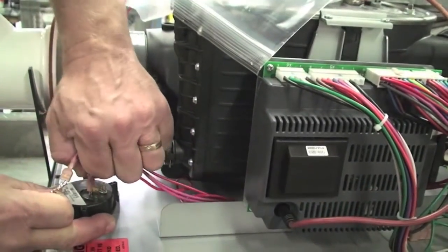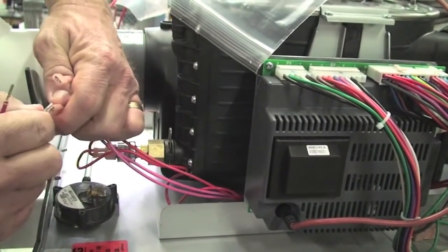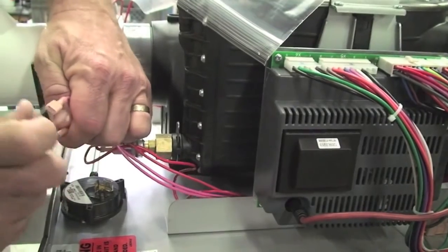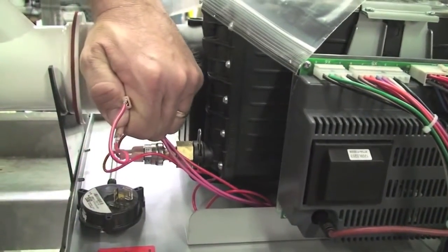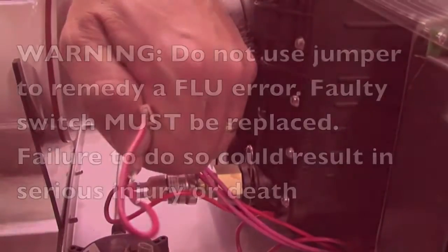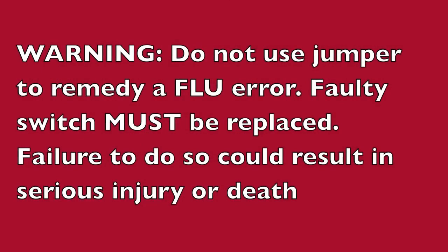Second, if the exhaust venting is fine, next jump out the switch to see if the unit resets and runs. Monitor the operation after replacing the switch, but never leave the switch jumped out as this could lead to an unsafe condition.